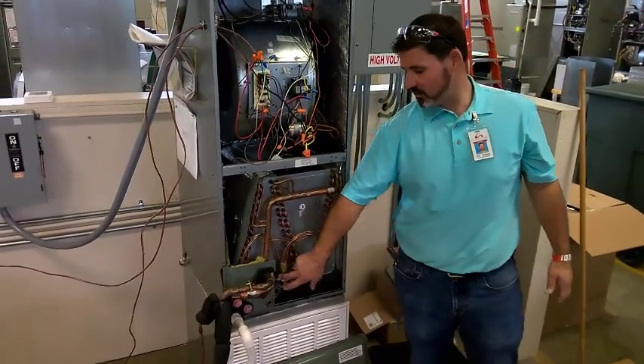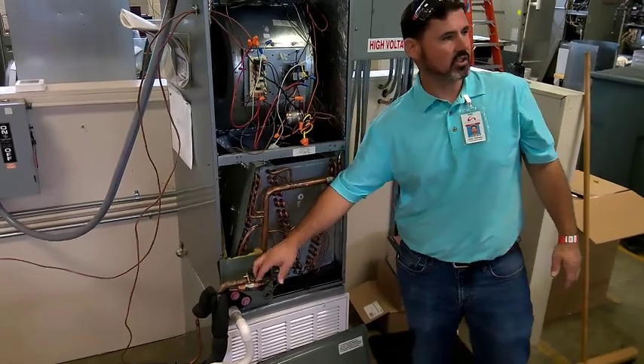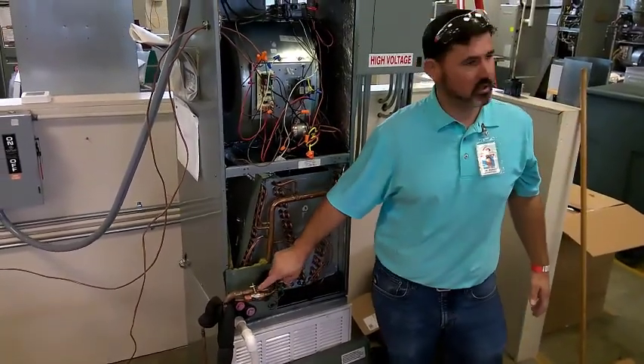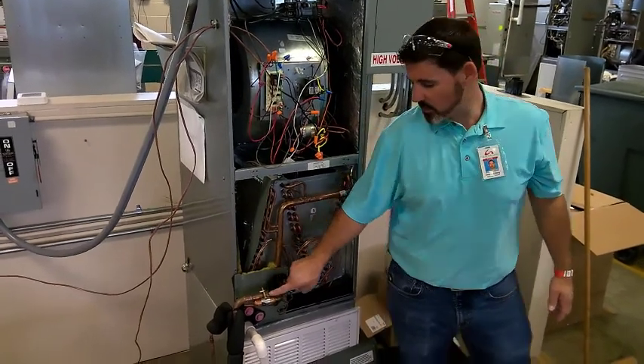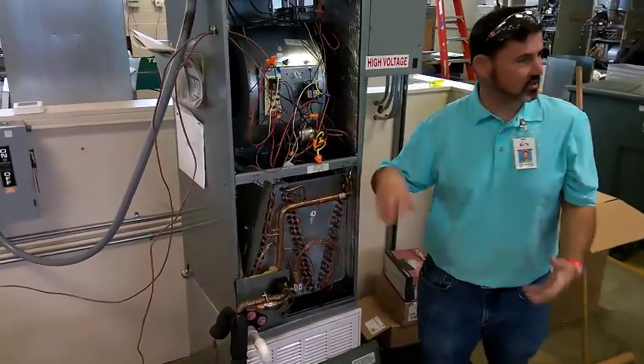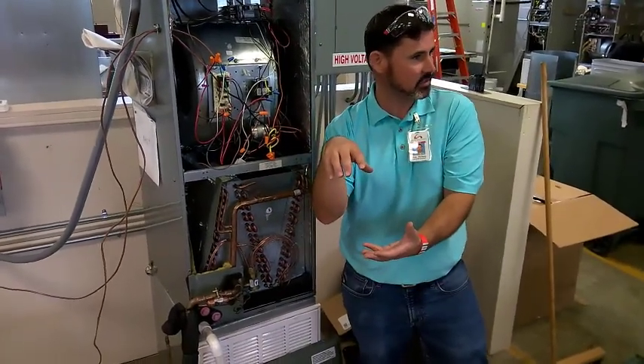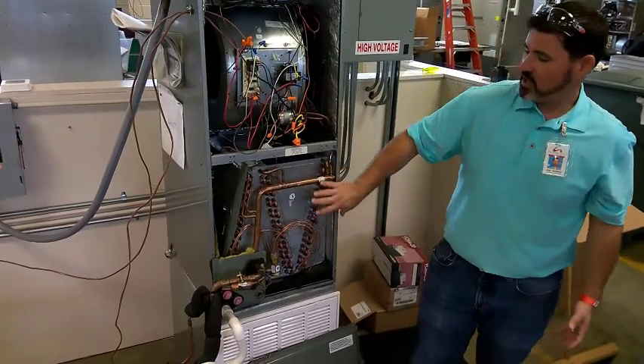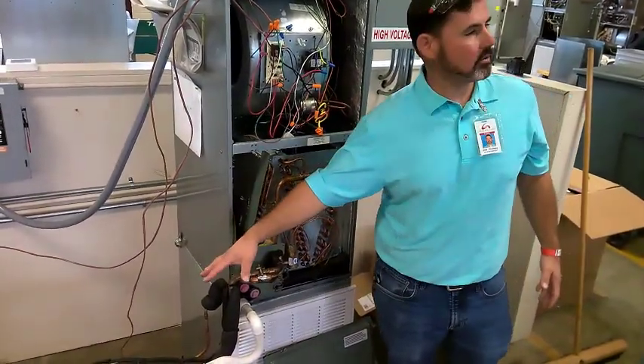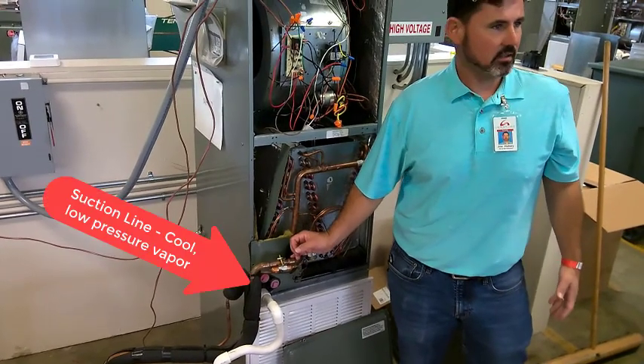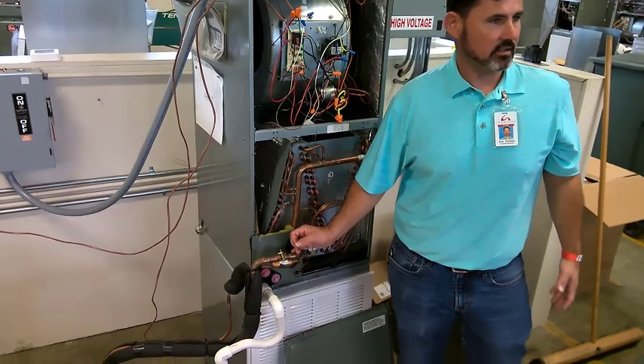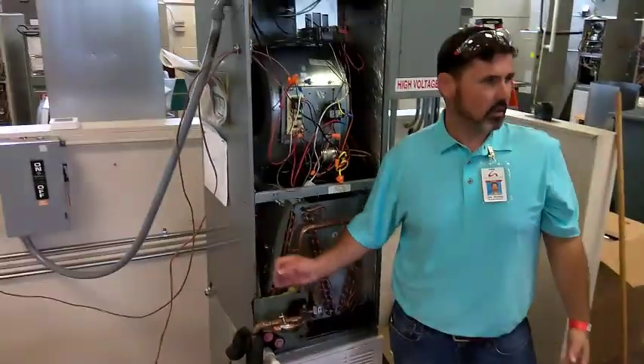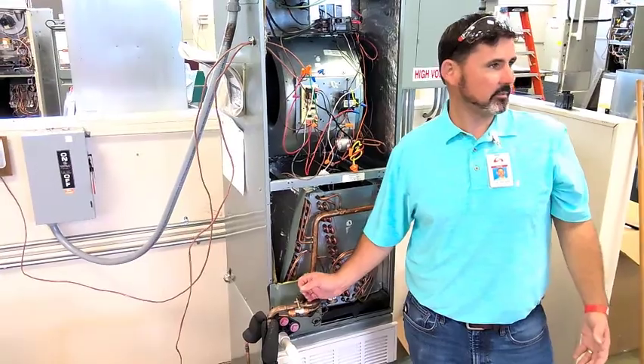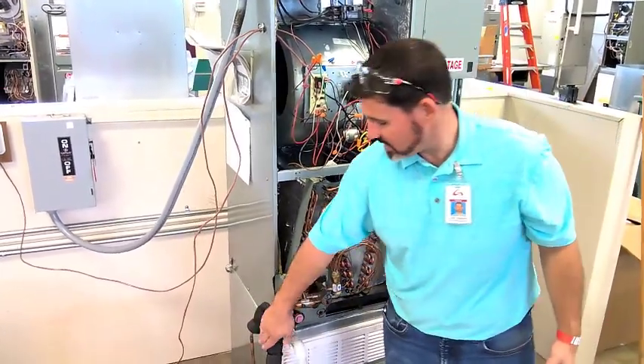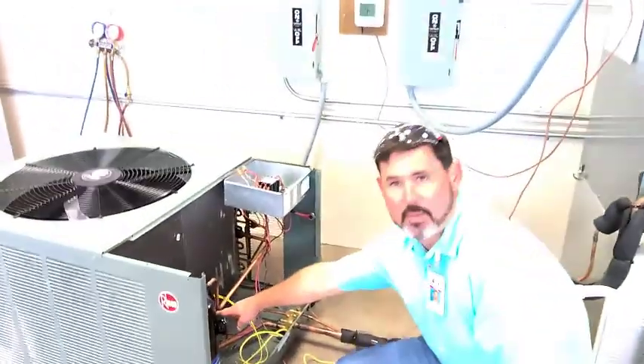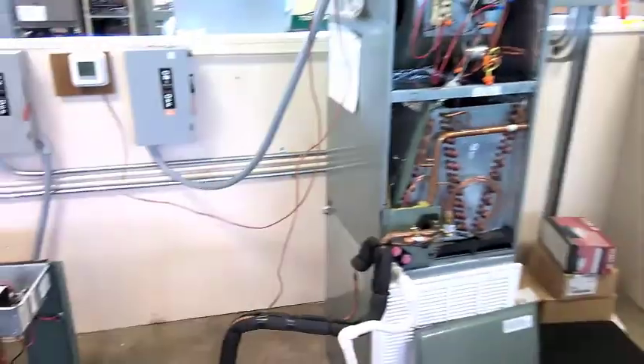So the job of this TXV is simply to maintain superheat. It's going to adjust how much refrigerant is allowed through this coil based off of the temperature of this copper pipe and my spring tension and the pressure. So it's doing a balancing act in there to keep it where it needs to be. All right. So once I finish going through here and evaporating, I come back to my compressor, and this is called the suction line. Suction line is cool, low pressure vapor. All right. This cool vapor is coming back on my suction line. It just goes right back to my compressor, and the cycle continues.